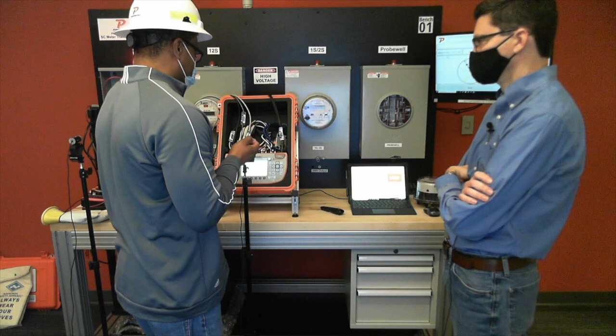So why go to meter test and not integrated site test? Because we're not testing the CTs, we're not doing anything like that. My bosses want me to get at least 15 to 20 meters done, self-contained, so I'm going to do a meter test — it's a lot faster.